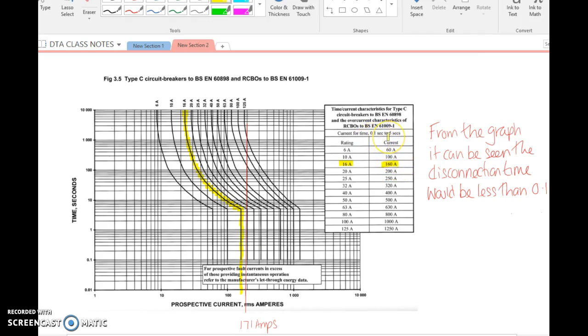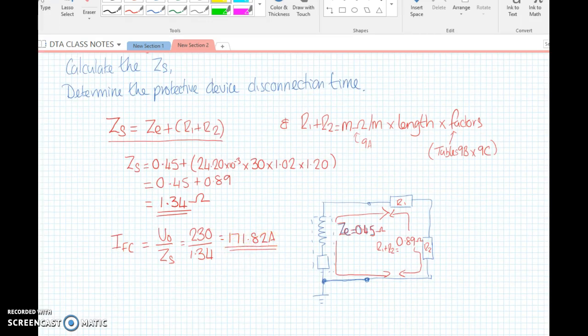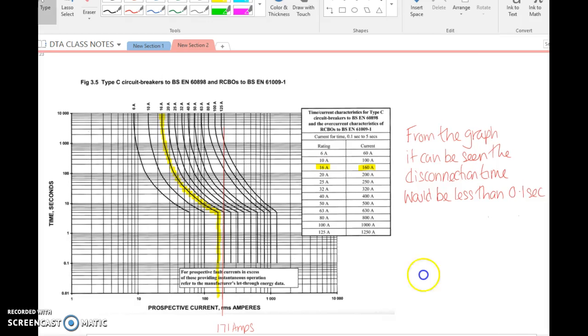You can see we're using the type C 60898. We look at the 16 amp curve, and on this table a 16 amp protective device needs a minimum fault current of 160 amps for it to go within 0.1 to 5 seconds. Ours is 171 amps because we just worked that out. If the fault current is greater than the minimum on here, then it would be an instant disconnection, so the disconnection time would be less than 0.1 seconds.